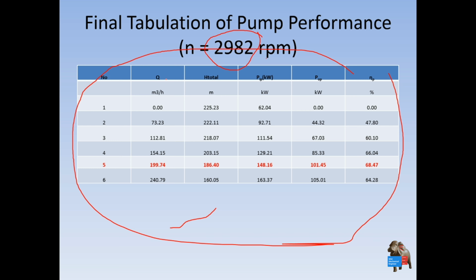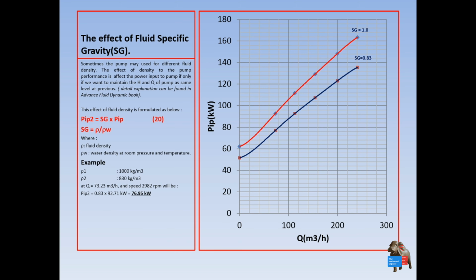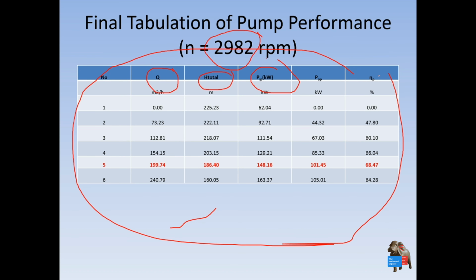For the correlation of the speed, of course you have to follow the affinity law. Head is exponential 2, power is exponential 3, and the correlation to the flow capacity is linear. After you get there, you will have the pump efficiency here. You also have the power output of the pump and the power input of the pump. I mean the power into the pump and the power output of the pump.